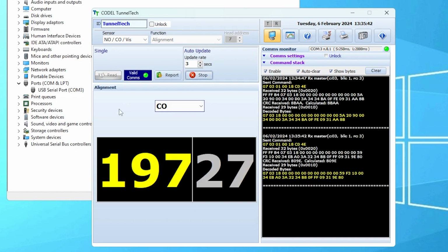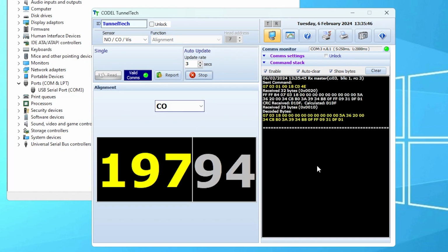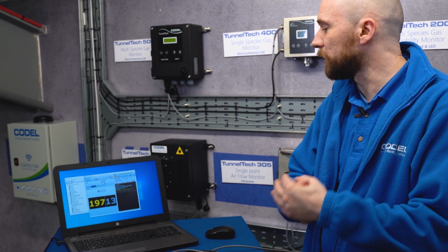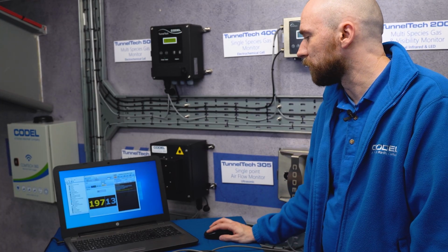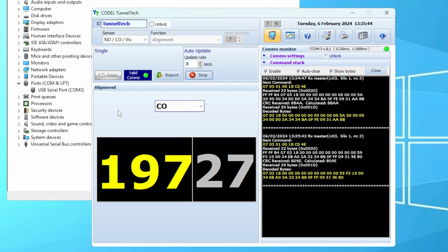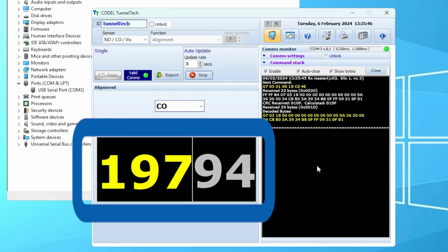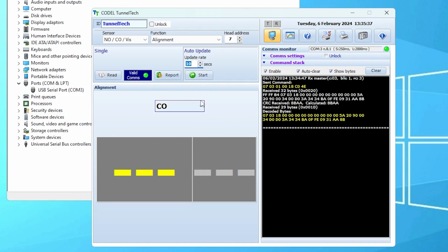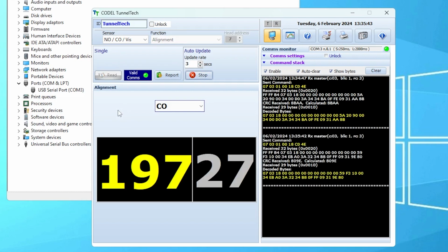And the whole purpose of the fine adjustment is to make adjustments on the alignment brackets as before, but in this circumstance, we're going to try and maximize the number displayed here on the alignment page. To do that, we can select an update rate of 3 seconds, click start, and now this system will be updating every 3 seconds so we can monitor the detector levels.